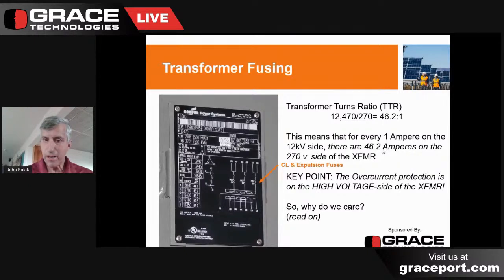And as engineers, we want to spec out which fuses, if you have a choice when ordering the transformers. Being able to pick the kind of fusing you're using can directly or greatly impact incident energy from the engineering side of the house. The other thing we're going to talk about is the transformer turns ratio. We're going to get to that in just a moment. But you'll actually see that on the left side of the transformer, there's a table A, B, C, D, and E. Those are the tap settings on the transformer itself.